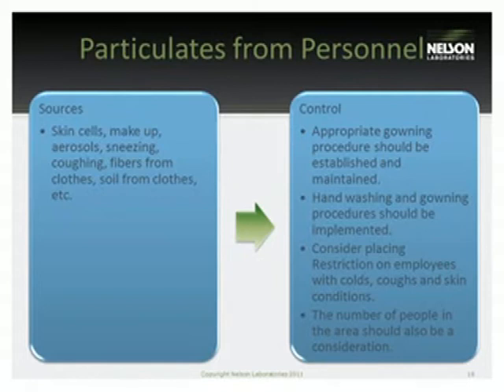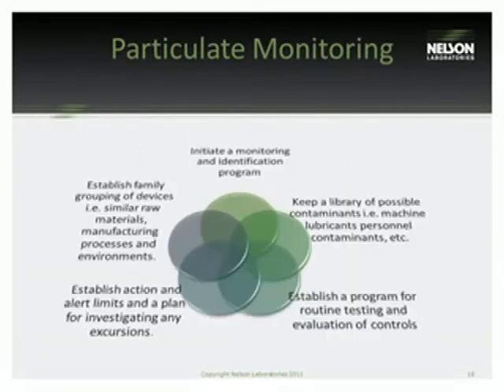Some controls that can be established, short of obviously classifying an environment, are appropriate gowning, hand washing, considering restrictions on the amount of employees or personnel in an area, and those that may be ill, have coughs or colds, skin conditions, that type of problem. Particulate monitoring, we do particulate monitoring here at Nelson just in our own areas. As a manufacturer, particulate monitoring is also a good way to keep an eye on the environment in which your device is manufactured, and to also help track down during investigations where particulate matter may be coming from if you're seeing a significant amount on your device.